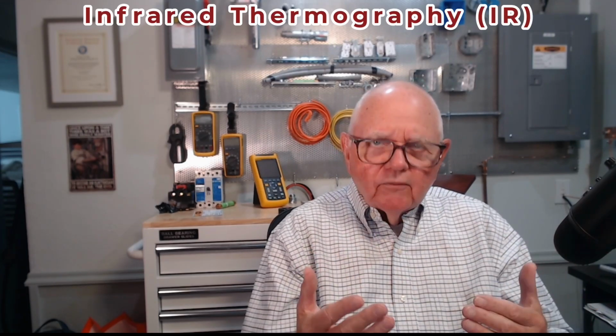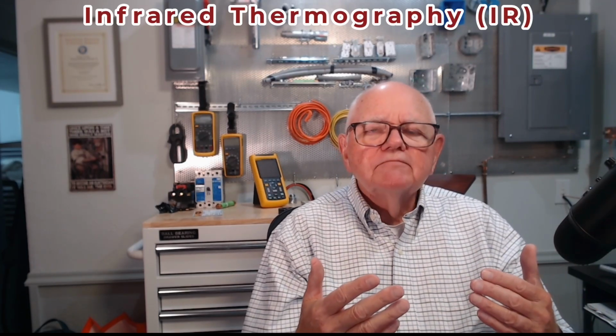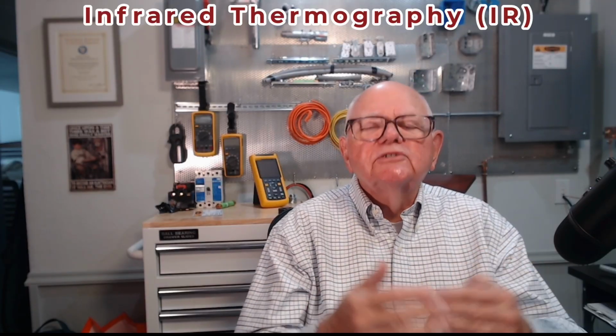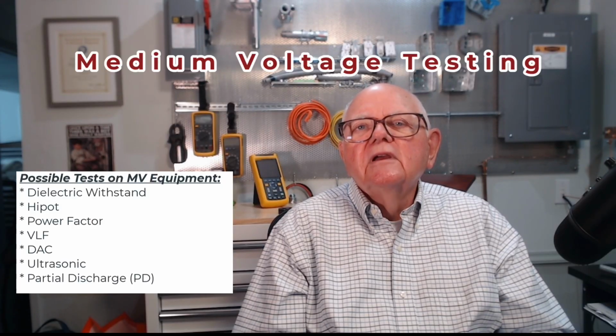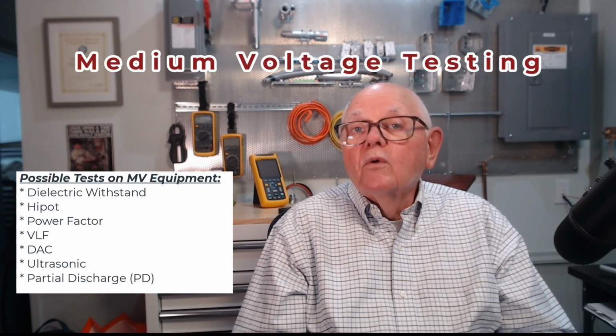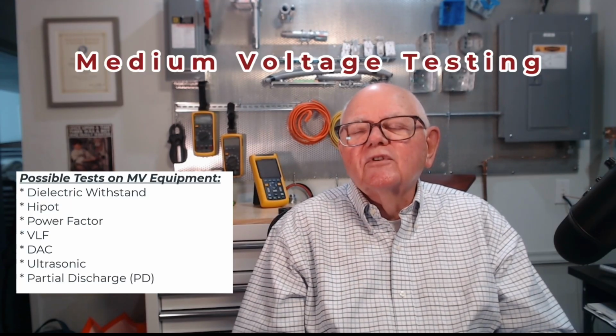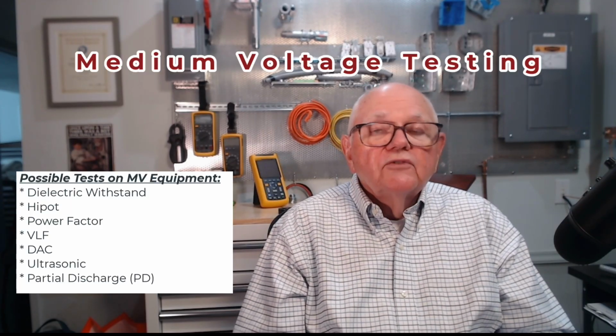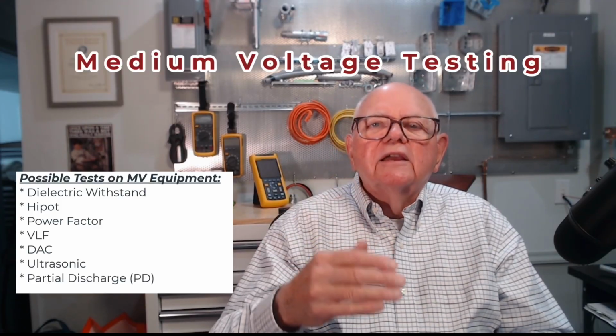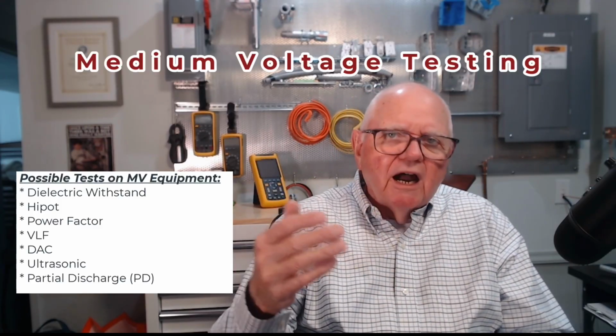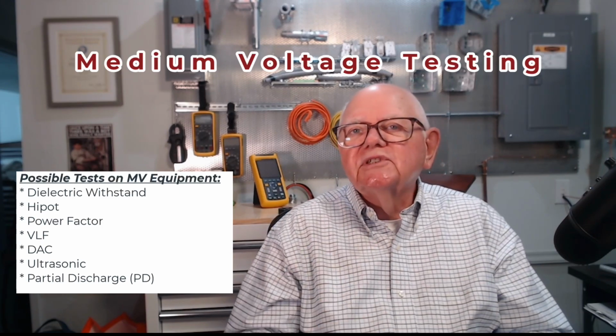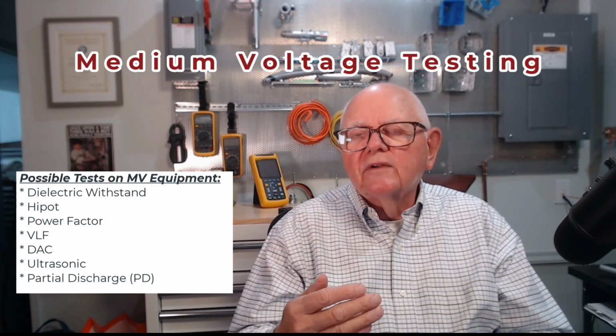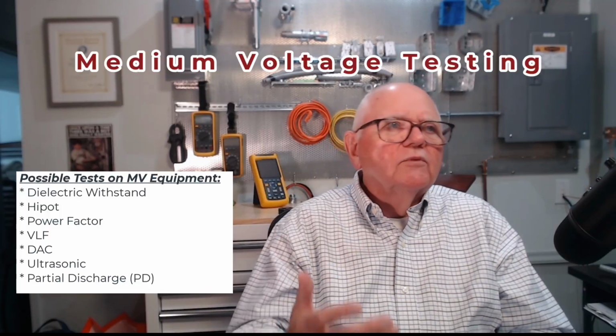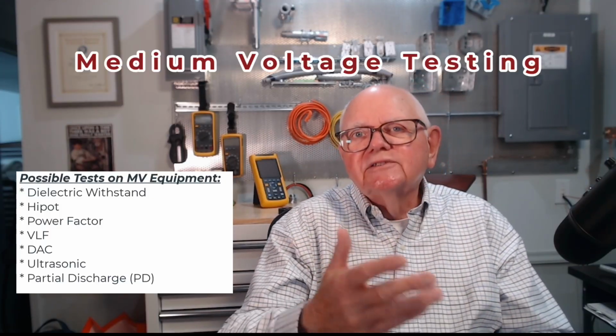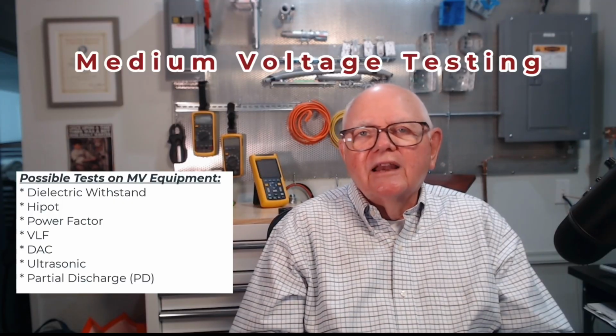If you work on any medium voltage equipment, as many of you do, right? For any medium voltage equipment, there's additional testing that you should perform as well. That's covered in the NFPA 70B standard, and it gives you a list of those tests. You must select from several different tests as to what you're going to perform. So on your medium voltage equipment, you may be doing things like high potential testing, high pot testing, VLF, very low frequency testing, tan delta testing, and so forth. Then we get into things like transformers, and we're measuring and testing oils, taking samples and sending them out for analysis and so forth.